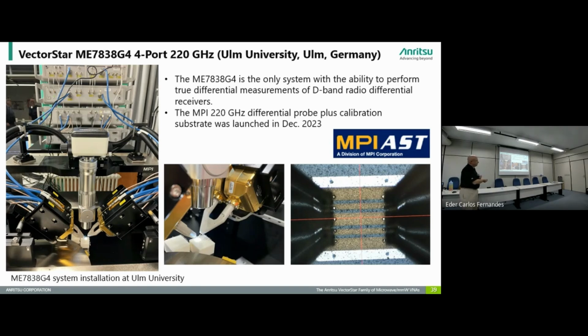You see these contact points here? These are the actual places that the probe is touching. So you don't want to be missing 2 down here, because then you obviously have a problem with planarity. Yeah, so that's where it becomes really challenging, is getting these mechanical systems set up perfectly so that when you touch down, you have the confidence that you're making contact properly on all of them. So this is really the most complex system that we can do today.